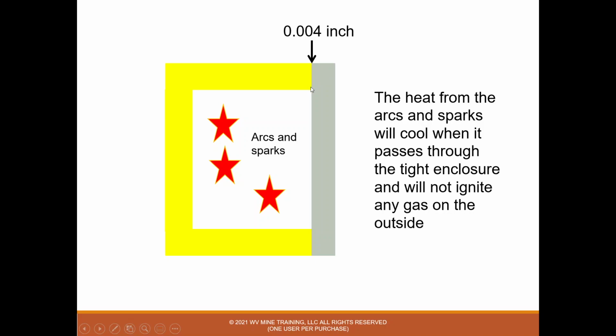But the heat that's created within that enclosure, by the time it reaches the outside, because it has to travel this tight gap of 0.004 of an inch, will cool it down. Will cool that heat down before reaching the outside, so that it will not be hot enough to cause a methane gas explosion on the outside. And that's part of maintaining permissibility. It's designed that way. It's designed to have that small 0.004 of an inch gap, so things will be cooled down before reaching the outside.